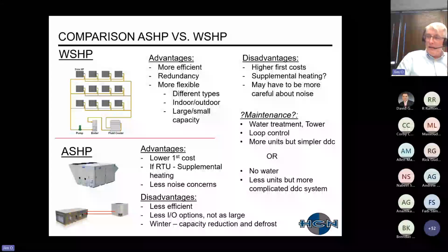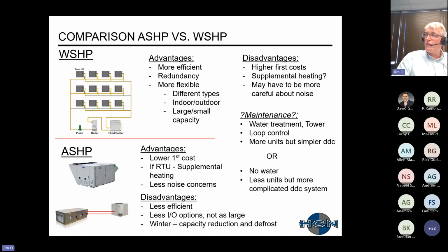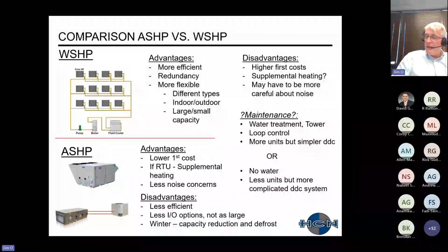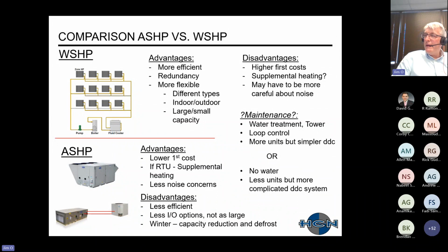Just wanted to touch on maintenance, probably cherry picking some of this. Obviously the water source heat pump has the additional thing of water treatment. You do have a control system that's pretty simple, but you do have a control system for the loop. And for air source heat pumps, it's obviously less maintenance for an air system versus water. From a maintenance perspective, traditionally you'll have fewer units to look at, but typically the DDC is more complicated than a simple water source heat pump that's 2 or 3 tons that has heating, cooling, maybe hot gas reheat, et cetera.